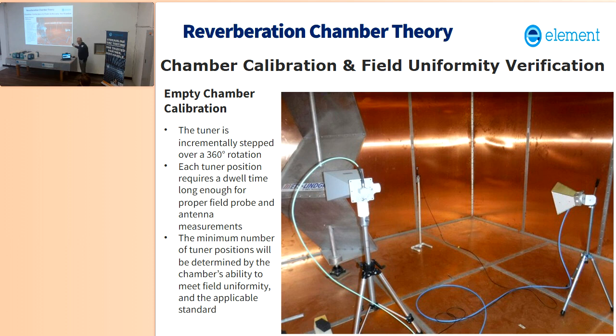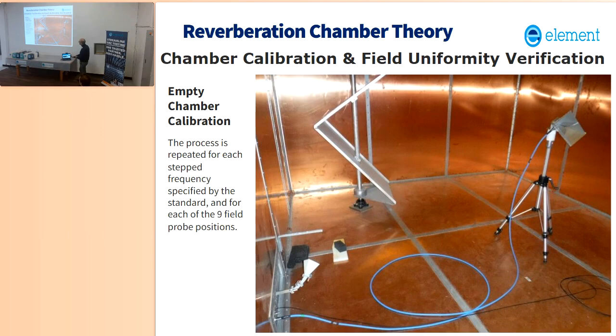So in here, did you do what, 10 degrees, 30 degrees? 10 degrees, yeah. And you use the same number of steps during the test as you do during the calibration. So you've got to use 10-degree steps during testing since you calibrated with 10-degree steps. And this process is repeated at every frequency for each of the 9 field probe locations. And you've got to do it at 50 or 100 frequencies per decade, from 100 megahertz up to 18 gigahertz. So long time. A lot of positions, a lot of frequencies, long time. Different antennas.